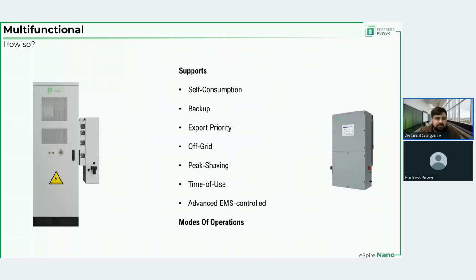About multifunctional, let me remind everyone that this system can support self-consumption, backup, export priority, off-grid, peak shaving, time of use, modes of operations, and even more complex strategies available with advanced EMS. That is for peak shaving and time of use. So you can do multiple peaks with the EMS rather than one peak threshold. And in terms of time of use, you're not limited to 6 charge and discharge intervals.